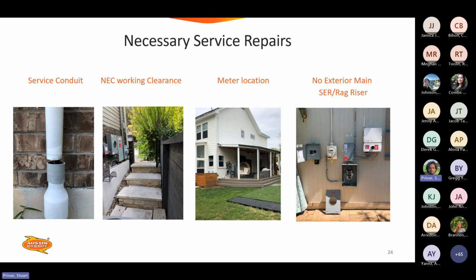It was originally built on the side of a house, but then a customer might build a porch or a deck over the revenue meter and sort of enclose it, which is a violation of the design criteria. So if that's the case, it's definitely beneficial to be aware of it before you install the solar system. That one, the switchgear that you can see, the solar has been installed, and the solar was good, except for the fact that the revenue meter can was in the wrong location. So they had to backtrack and do an expensive relocation of the main service.